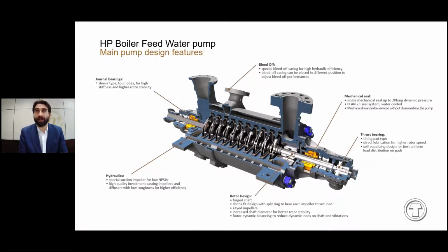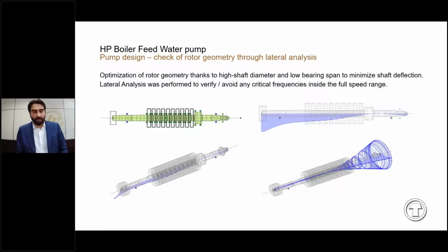The impeller has a shrink fit design on the shaft, which is forged, and this kind of design is very important in order to reach a very high level of dynamic balancing on the rotor. That means very low dynamic loads and vibrations. The rotor of the pump has been sized with a very big diameter and low bearing span in order to minimize the shaft deflection at startup.